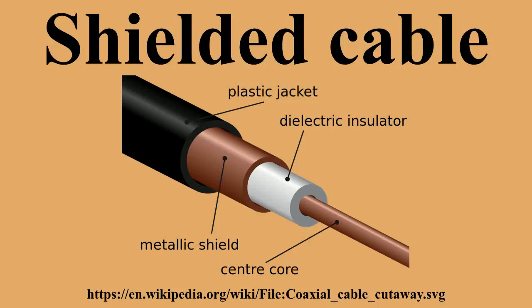Stress relief cones should be applied at the shield ends, especially for cables operating at more than 2 kV to earth. Shields on power cables may be connected to earth ground at each shield end and its splices for redundancy to prevent shock, even though induced current will flow in the shield. This current will produce losses and heating and will reduce the maximum current rating of the circuit.